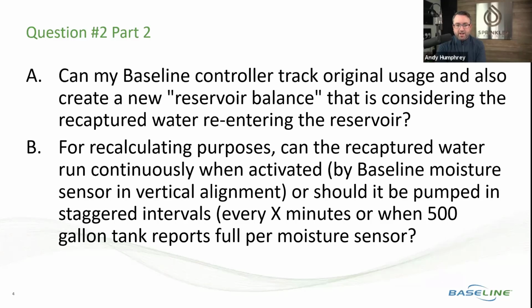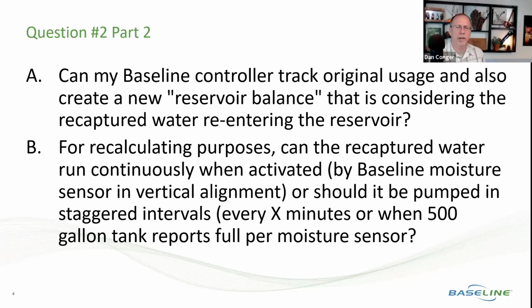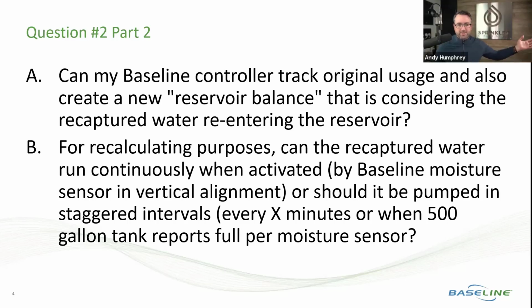There are a couple of key statements here. Can we track original water usage? Yes, because we can put a flow sensor anywhere, right, and at one controller we could put 8 of them and track whatever water usage we want. The second part of this is creating a balance. Now, what we can't do is math between flow sensors, right, we can't say this flow sensor subtract this flow sensor equals some other number and do something with that other number.